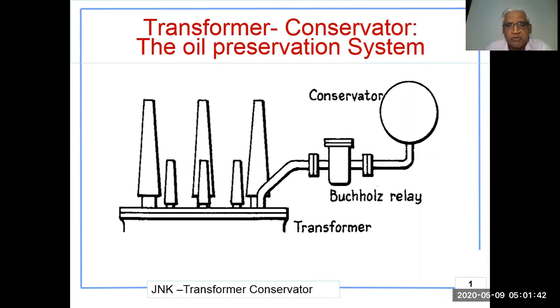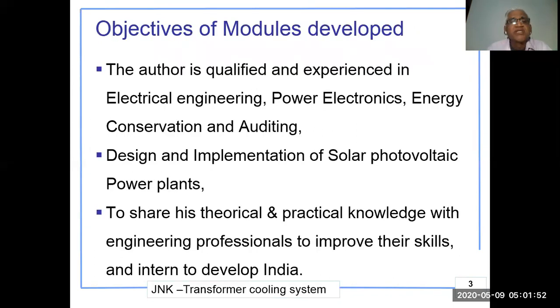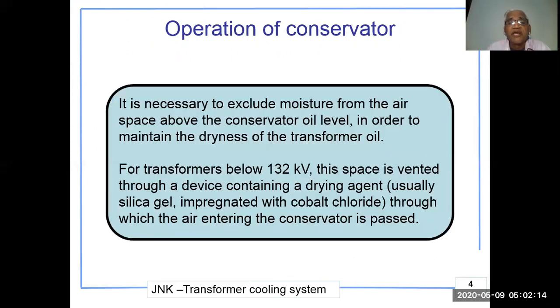Today the topic is transformers — specifically the conservator, also called the oil preservative system. The module author is qualified and experienced in electrical engineering, power electronics, energy conservation, auditing, and design and implementation of photovoltaic power plants, aiming to share theoretical and practical knowledge with engineering professionals. Now, regarding the operation of the conservator: it is necessary to exclude moisture from the air space above the conservator oil in order to maintain the dryness of the transformer oil.